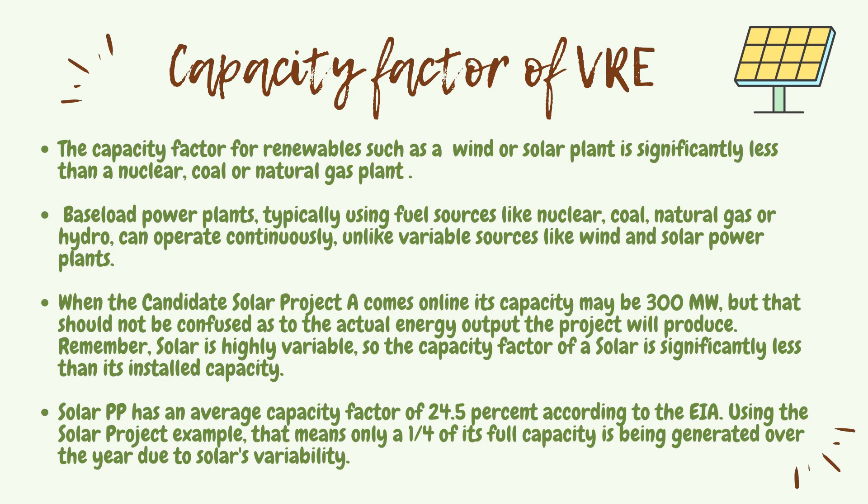For instance, when a candidate solar project comes online, its installed capacity may be 300 megawatts, but that should not be confused with the actual solar output the project will produce. Remember, solar is highly variable, so the capacity factor of a solar power plant is significantly less than its installed capacity.